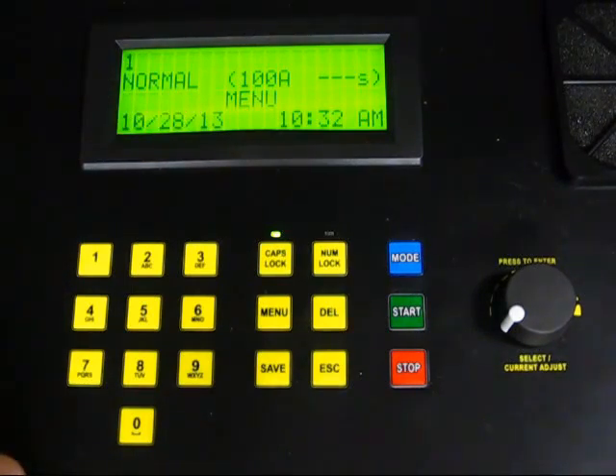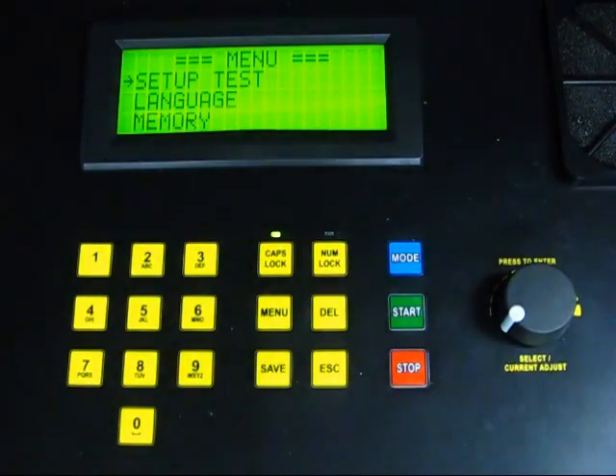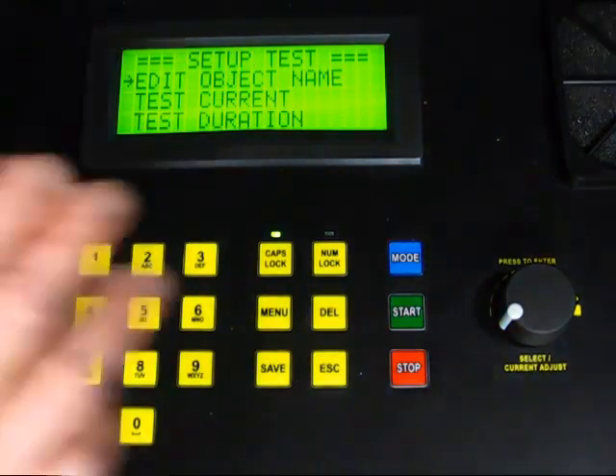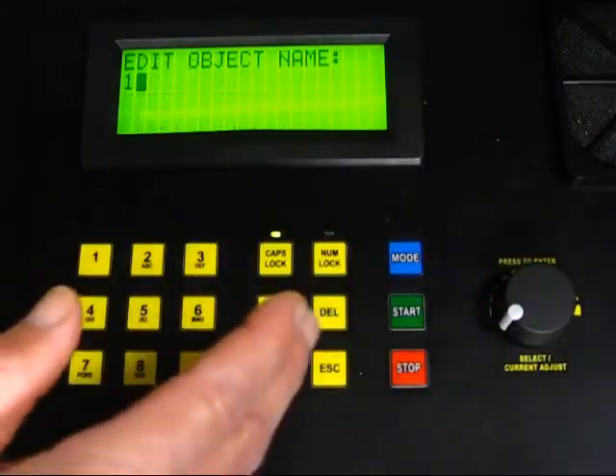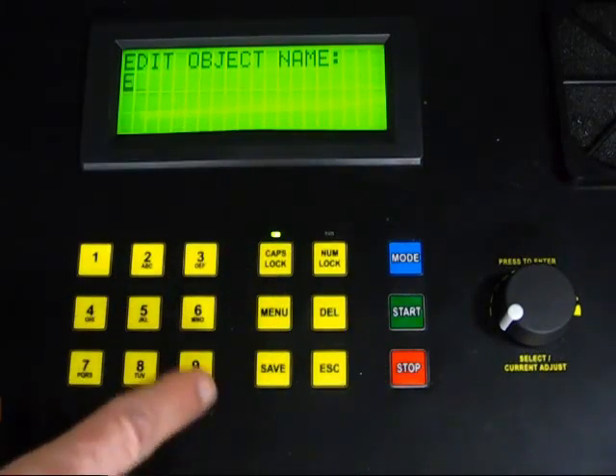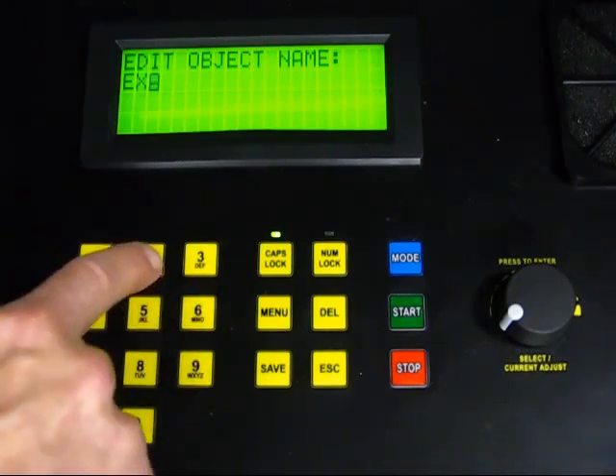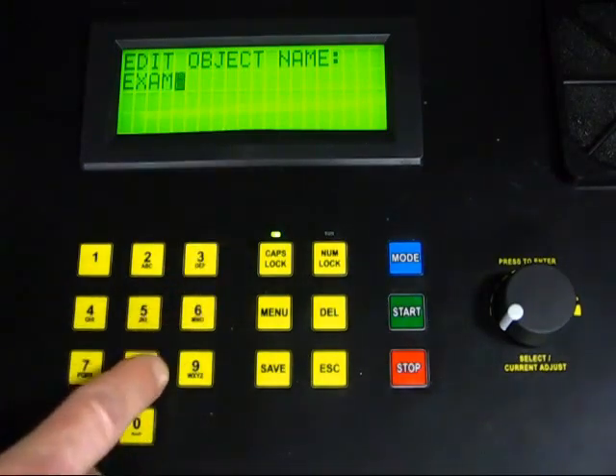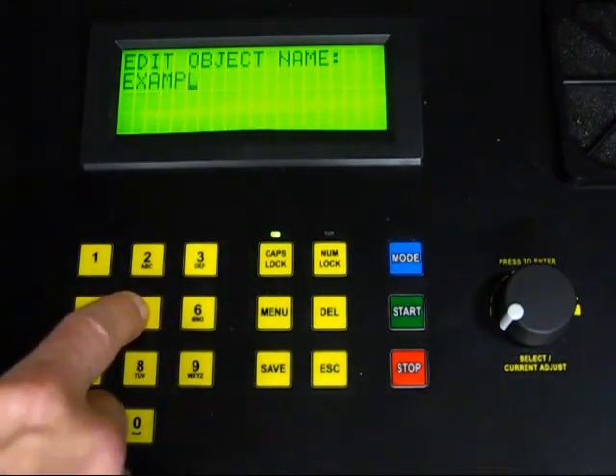We will now set up and run a test on the 6292. To set up the test, push the Menu function key. This displays the main menu. Select the Setup Test option by pressing down briefly on the rotary knob. The Setup Test menu appears. Select the option Edit Object Name by pressing on the rotary knob. Tests performed on the Model 6292 are stored in data records called objects. Each object can contain multiple tests. For our demonstration, we will name our object Example 1 using the alphanumeric keypad. After entering the object name, press the rotary knob to save it and return to the Test Setup menu.